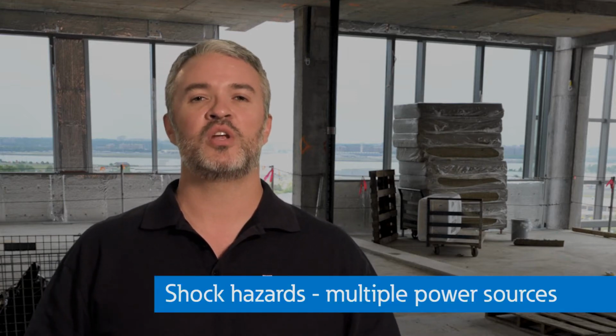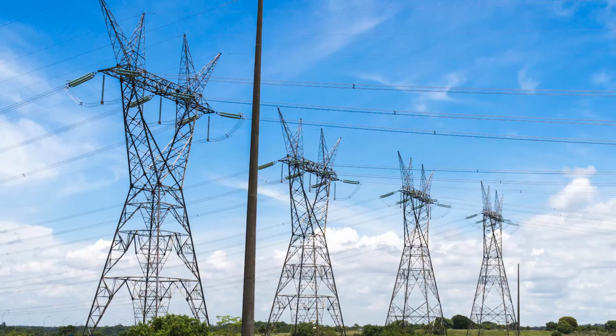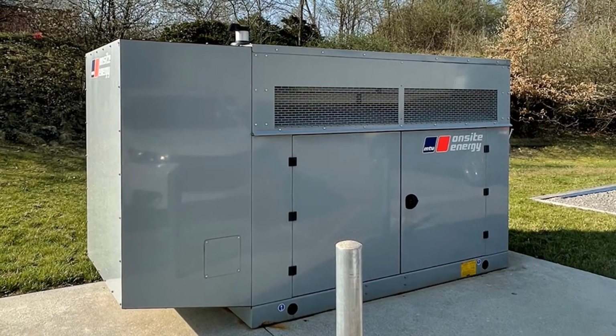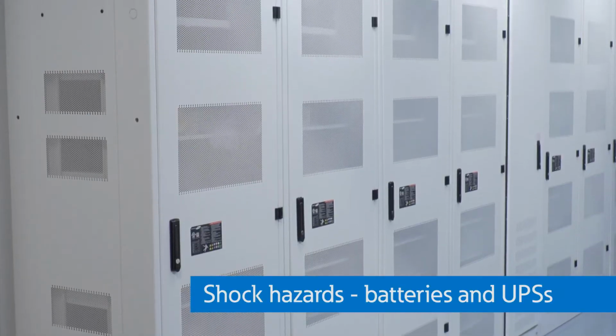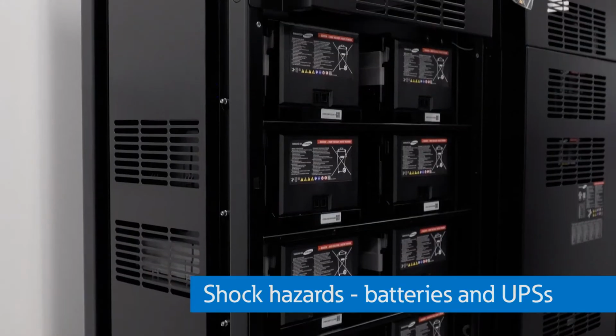You have likely attended OSHA electrical safety training, which highlights the key points of shock hazards. OSHA has strict guidelines in place for not only the designs of electrical systems, but also safety-related work practices. This training applies in hospitals, but you should give special consideration to shock hazards associated with multiple sources of power, including sources from the utility, generators, or both. In addition, you also have to be aware of DC sources like batteries and UPSs to protect you from shock hazard. A hospital is usually fed from at least two sources of power with generator backup.